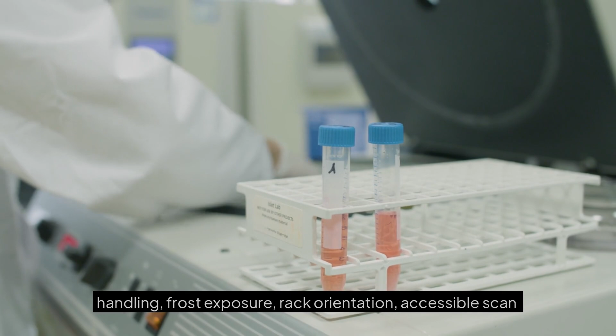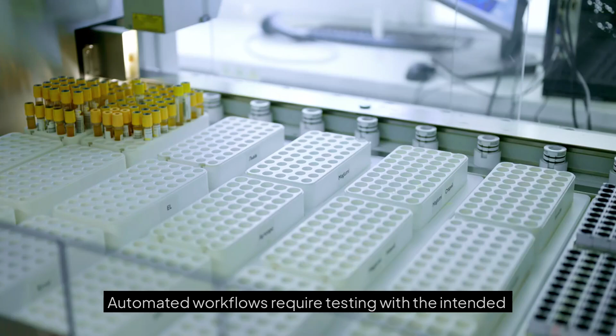Representative retrieval testing should include gloved handling, frost exposure, rack orientation, accessible scan angles, repeat retrieval, and the intended time outside storage. Reader settings, rescan rules, difficult code locations, and observed failures should be recorded. Automated workflows require testing with the intended rack and equipment combination. Qualification then becomes a controlled sequence.